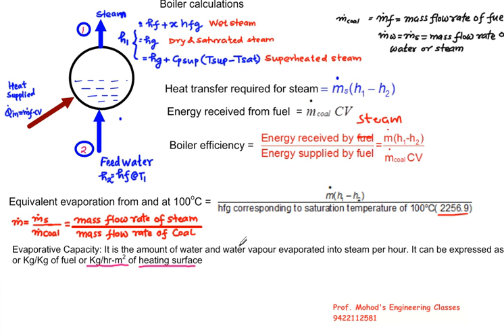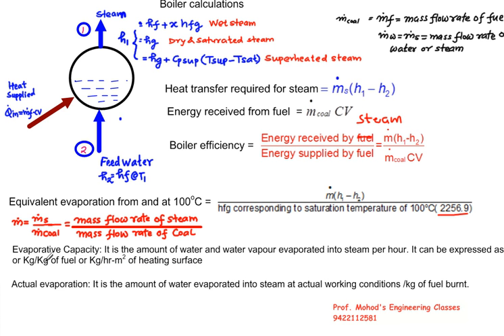Evaporative capacity is the amount of water and water vapor evaporated into the steam per hour. It can be expressed as kg per hour, kg of kg of fuel, kg per hour meter square of heating surface. Actual evaporation is defined as the amount of water evaporated into the steam at actual working condition per kg of fuel burn. These are the measures of boilers and boiler efficiency we do for performance. To compare the different boilers we are using equivalent evaporation or actual evaporation.